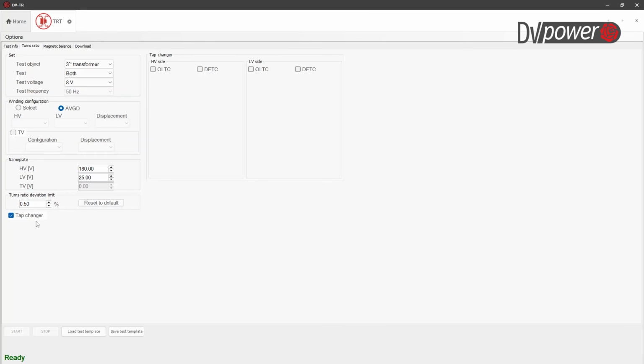We select tap changer button, and we select that on the high voltage side there is on-load tap changer in this case, but other options are also available for different scenarios. OLTC, we have 5 taps, and we will enter high voltage value for first and last tap.